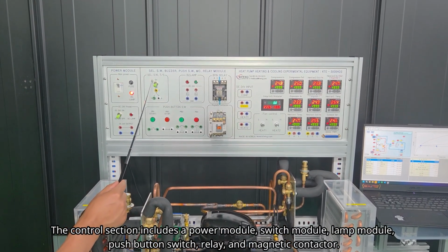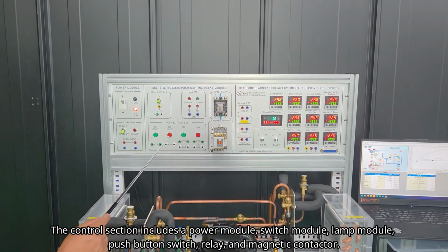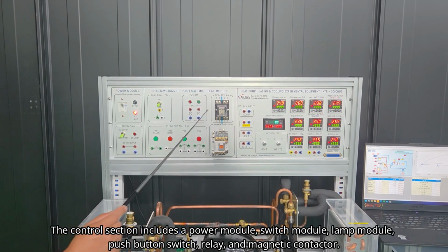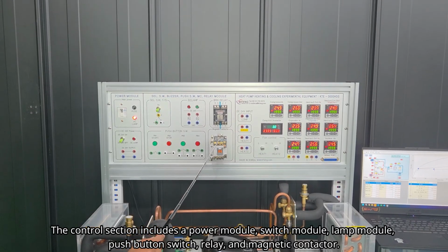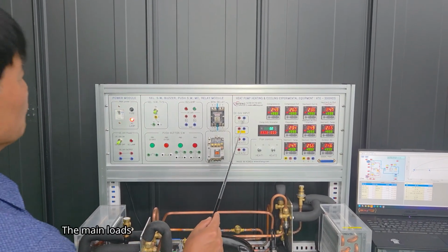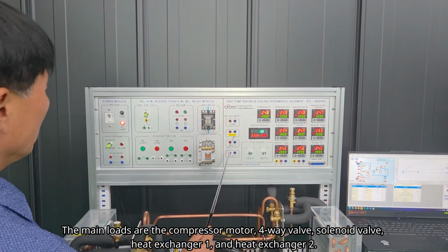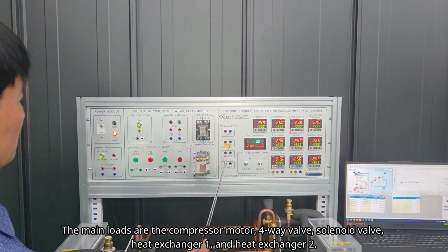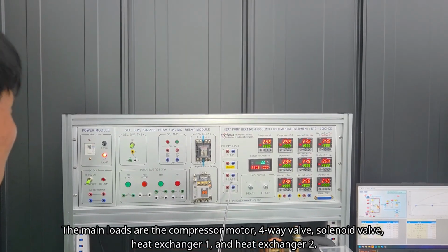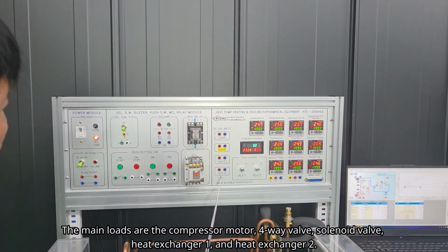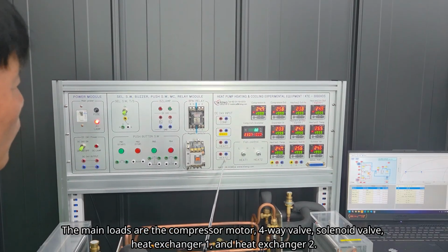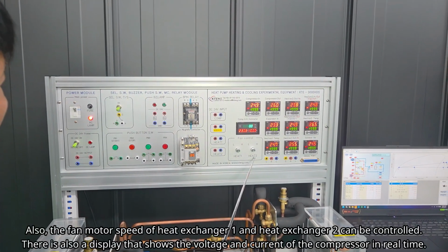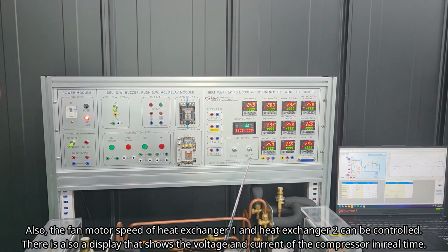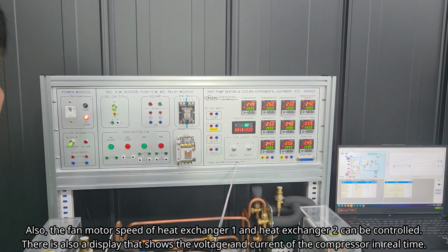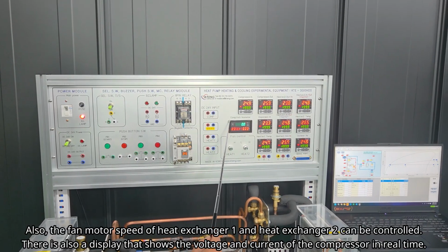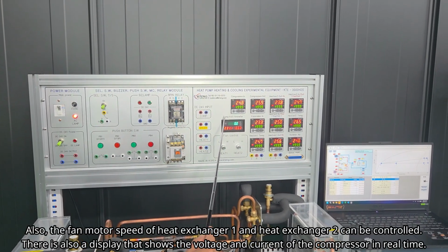The control section includes a power module, switch module, lamp module, push button switch, relay, and magnetic contactor. The main loads are the compressor motor, four-way valve, solenoid valve, heat exchanger 1, and heat exchanger 2. Also, the fan motor speed of heat exchanger 1 and heat exchanger 2 can be controlled. There is also a display that shows the voltage and current of the compressor in real time.